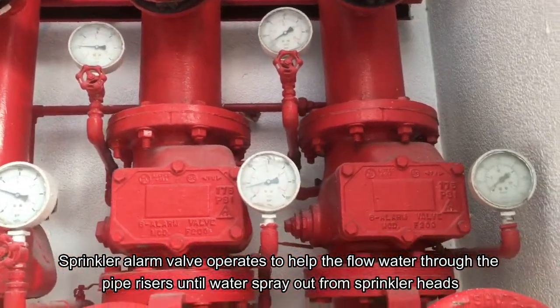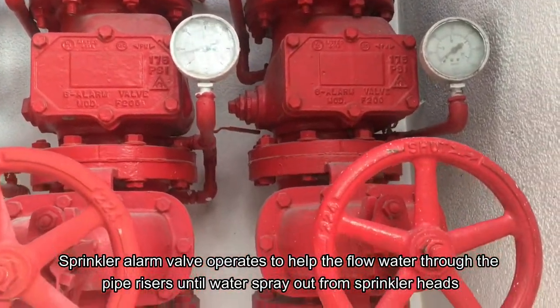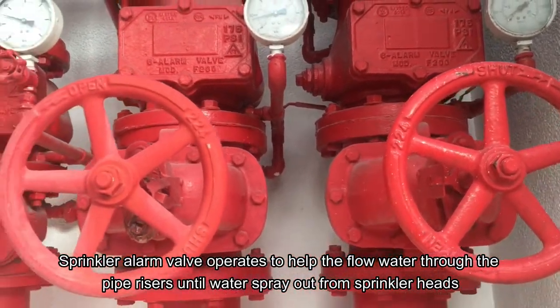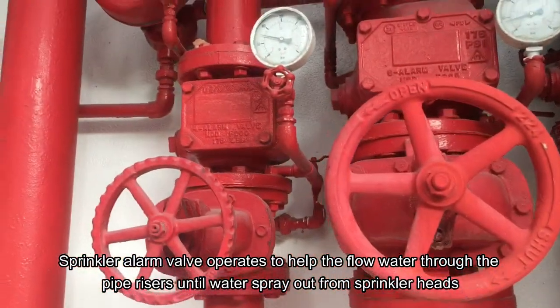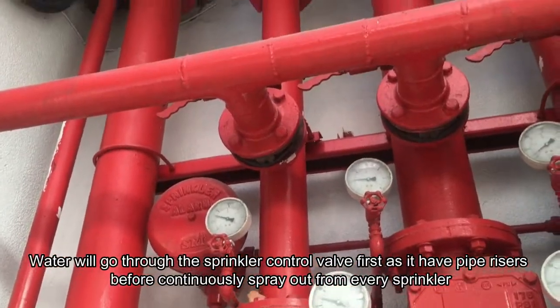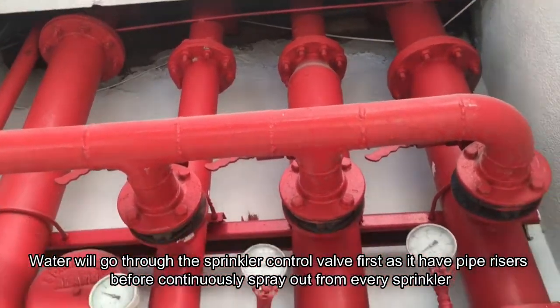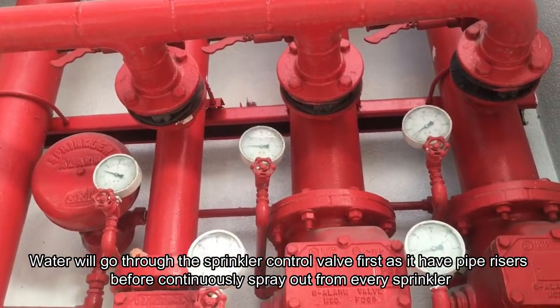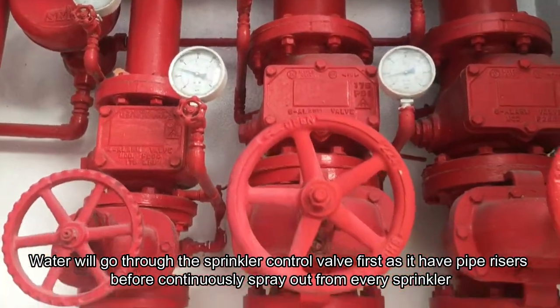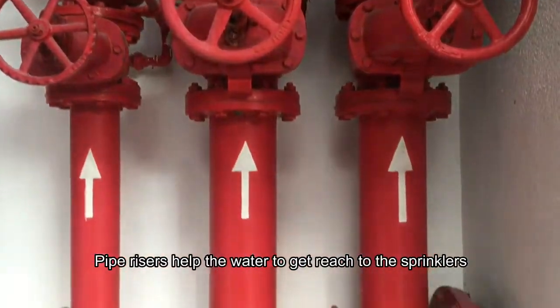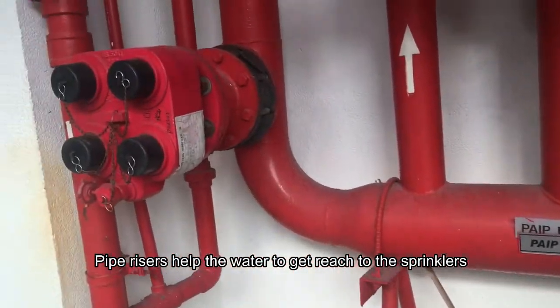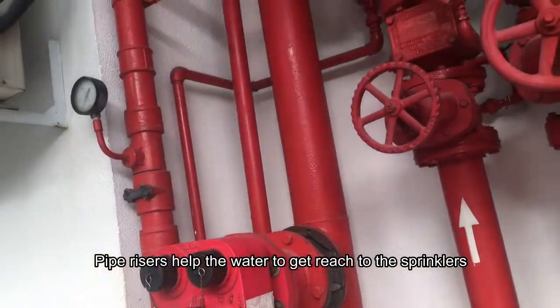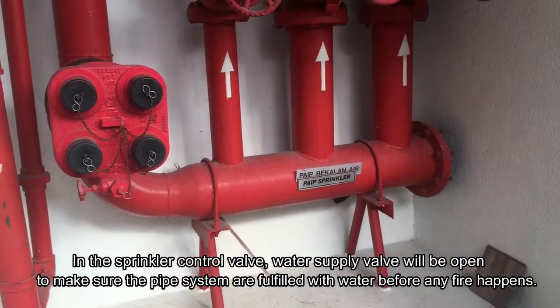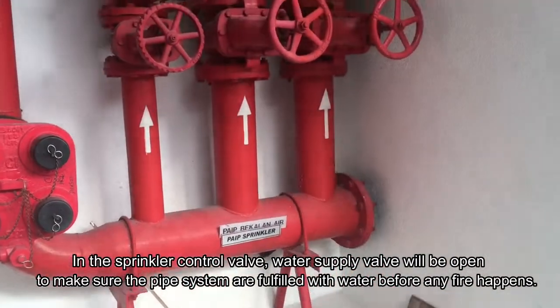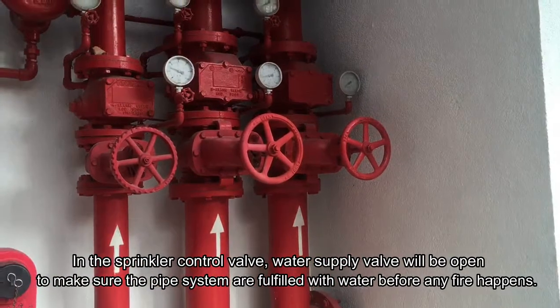Next is the sprinkler alarm valve. The sprinkler alarm valve operates to help the water flow through the pipe risers until water sprays out from the sprinkler heads. First, water will go through the sprinkler control valve, as it has pipe risers, before continuously spraying out from every sprinkler. Second, the pipe risers help the water reach the sprinklers. In the sprinkler control valve, the water supply valve will be opened to make sure the pipe system is filled with water before any fire happens.